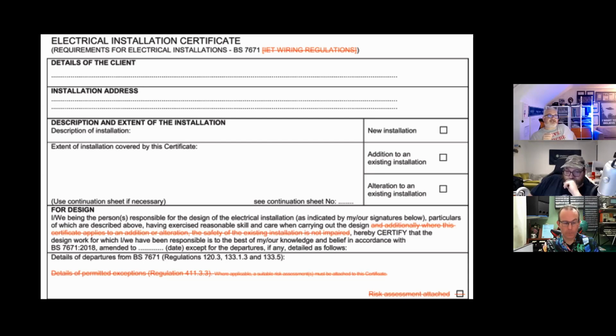Let's get it changed. I don't agree with that, Richard. The times 5 was always adopted because of the requirement for additional protection saying that 40 millisecond test, and the way to achieve that would be at 5 times I delta n. That moved in the 18th edition from 415.1.1 into part 6, and it's now just vanished.